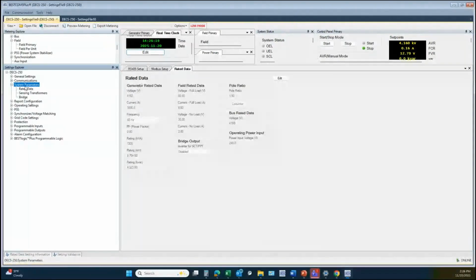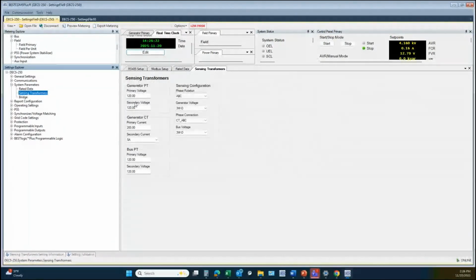So back in system parameters in our settings menu tree, if we go to sensing transformers, this is where we would set up any sensing transformer ratios that we might have. 4160 machine maybe is 4200 for primary and 240 volt secondary. And then this is also where you would define whether you have a 1 amp or 5 amp CT, and then what that primary current is. Again, the bus is not necessary unless you are actually sensing bus voltage.